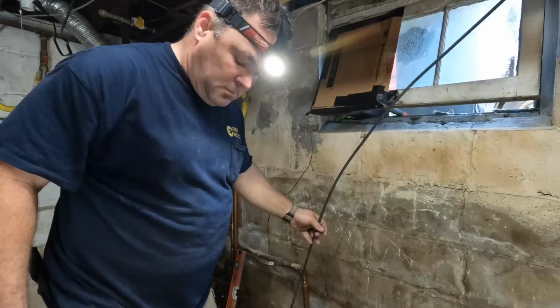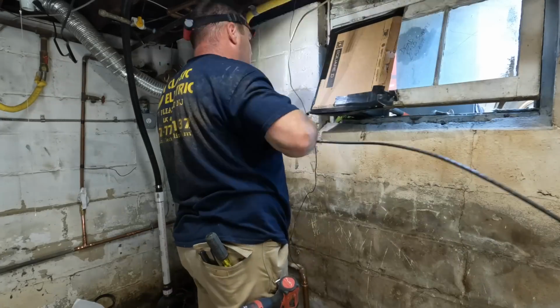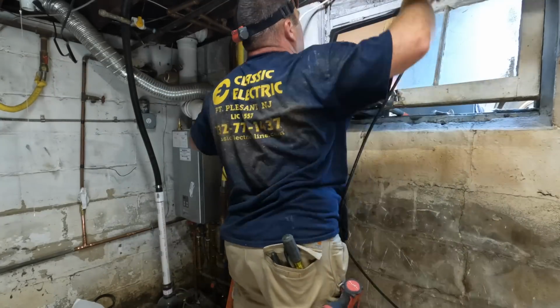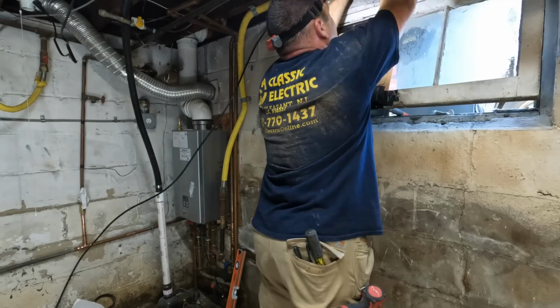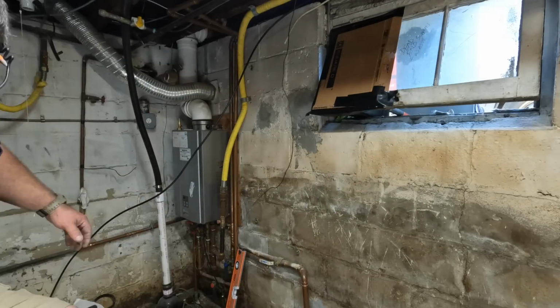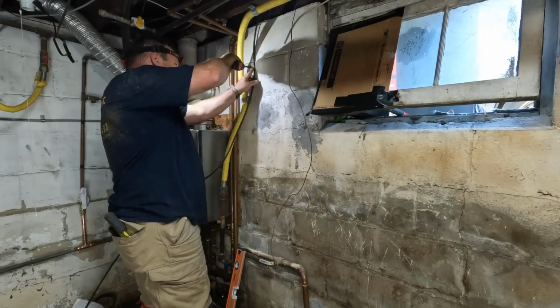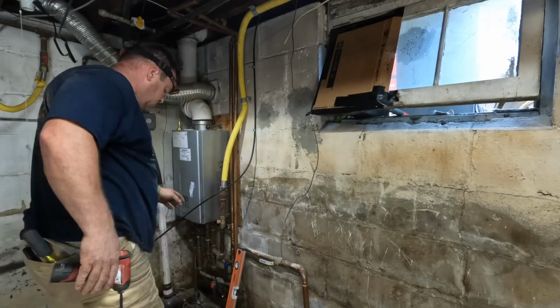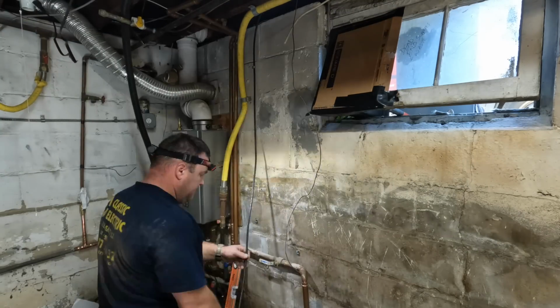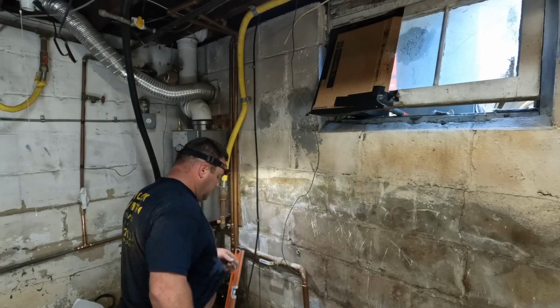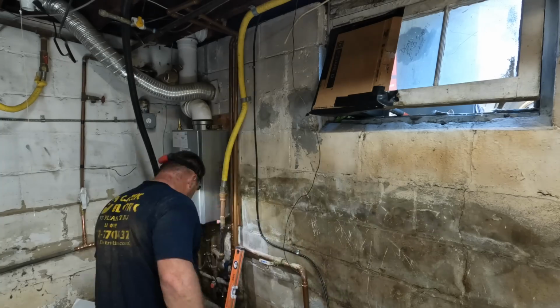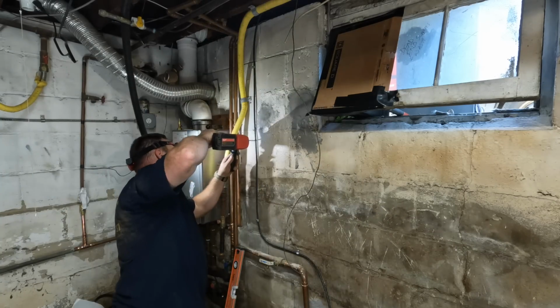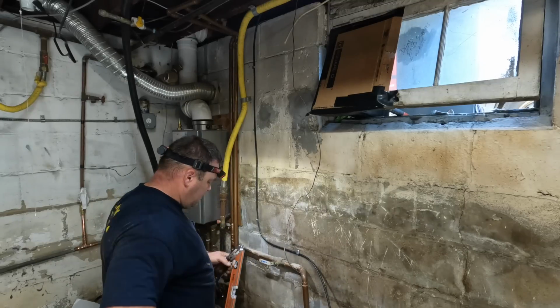Obviously, you see there's no meter, but you can see a disconnect valve right there. And then within the first 5 feet is where the National Electrical Code requires that we bond to the copper water main. And the copper water main needs to be at least 10 feet of copper inside the earth to qualify as a grounding electrode that needs to be bonded.